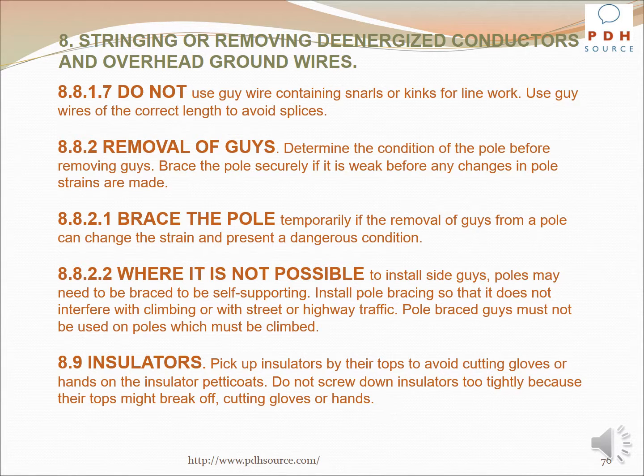Determine the condition of the pole before removing guys. Brace the pole securely if it is weak before any changes in pole strains are made. Brace the pole temporarily if the removal of guys from a pole can change the strain and present a dangerous condition. Where it is not possible to install side guys, poles may need to be braced to be self-supporting. Install pole bracing so that it does not interfere with climbing or with street or highway traffic. Pole braced guys must not be used on poles which must be climbed.